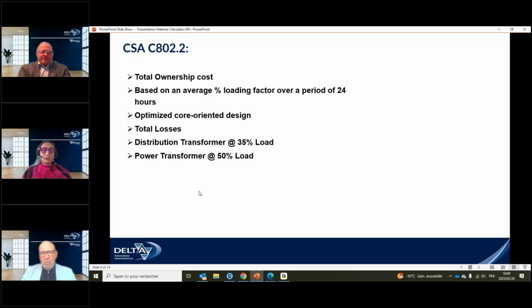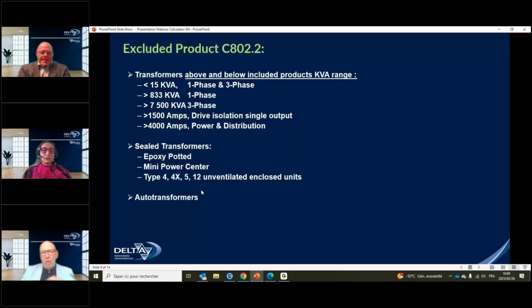Also, an important note: not all transformers are included in the CSA C802.2 standard. It's quicker to just talk about what is excluded. Mainly, single phase and three phase: anything below 15 kVA is excluded from that standard. Any single phase transformer above 833 kVA is excluded. Any transformer above 7.5 MVA is excluded. Any distribution or power transformer exceeding 4,000 amps on the secondary is excluded.